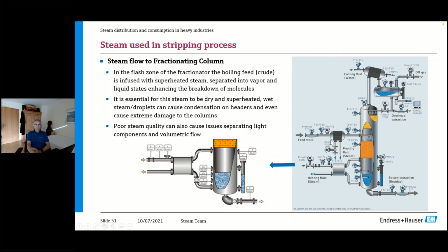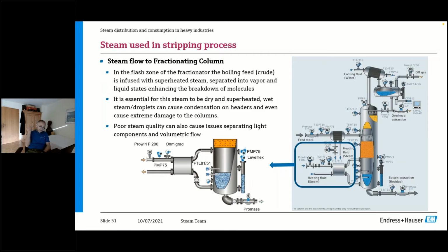For the mainstream, typically you find our Coriolis meters, temperature, pressure. But another important measurement, I'm going to come to that, is the guided wave radar for the bottom zone, for the bottom extraction for the residue. So typically you're going to end up with the FMP54 in that case. We're going to talk about that. Then for the stripping steam measurement, you need a vortex and pressure and temperature. And meanwhile, our recommendation is to use this one with the integrated pressure and temperature measurements, because then you also know the dryness fraction of the steam. The dryness fraction, for the heat exchangers but also for the stripping steam, has a lot of meaning, because only then you know the true energy of that steam going into your fractionating column. And this is something only Endress+Hauser can actually offer you.